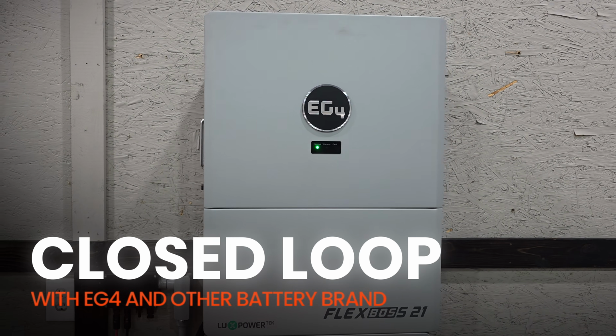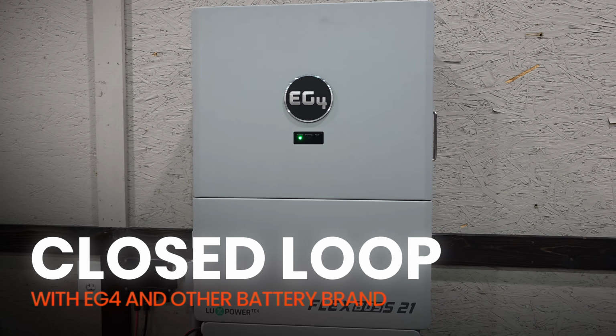EG4 also lists closed loop communication support with EG4 batteries and some other battery brands. That is important because closed loop communication allows the inverter and battery to communicate more intelligently. Things like state of charge, your charge limits, your discharge limits, your warnings, and your battery status can all be shared between the battery and the inverter. That can help with the system operating more safely and more predictably.